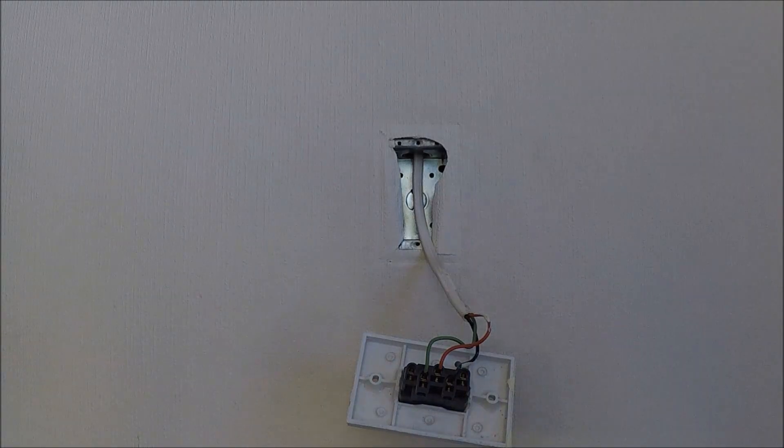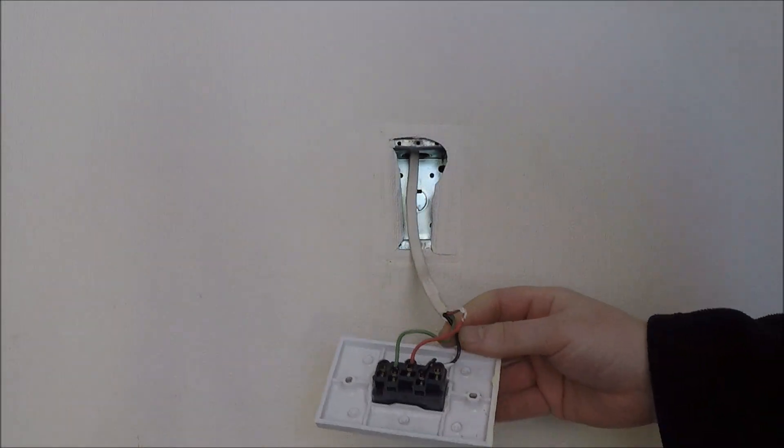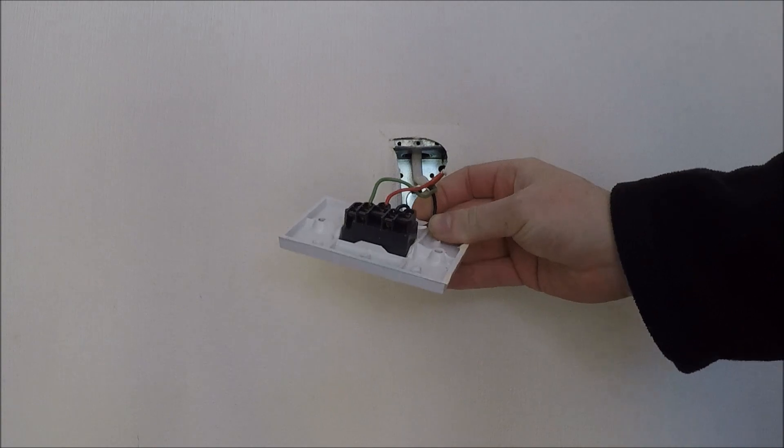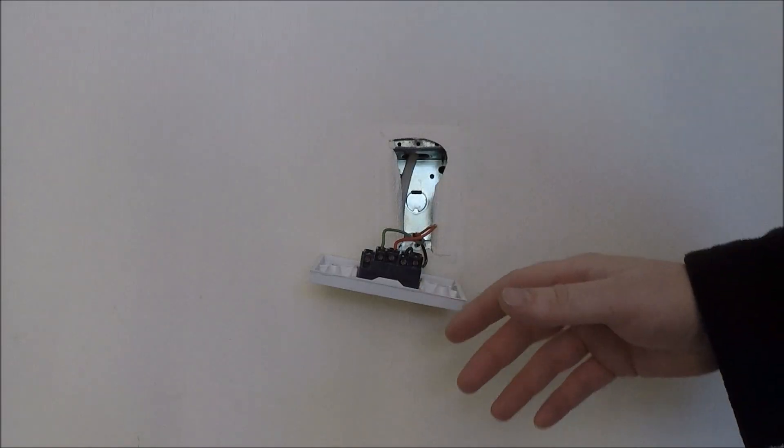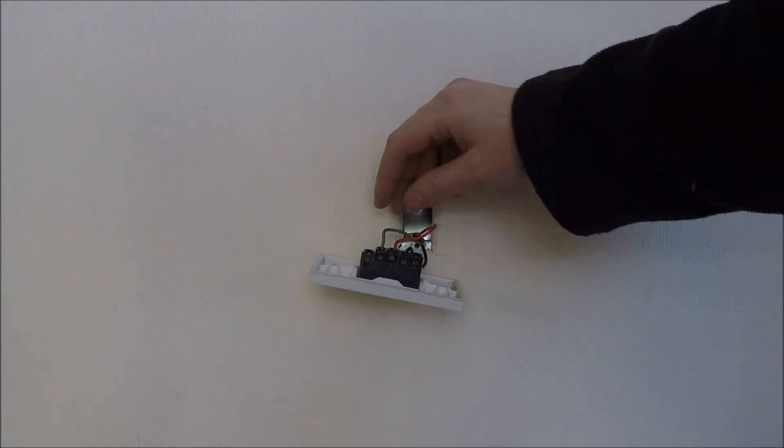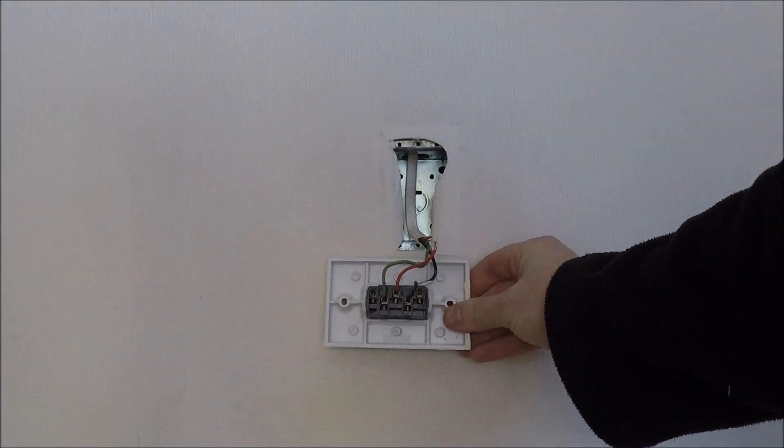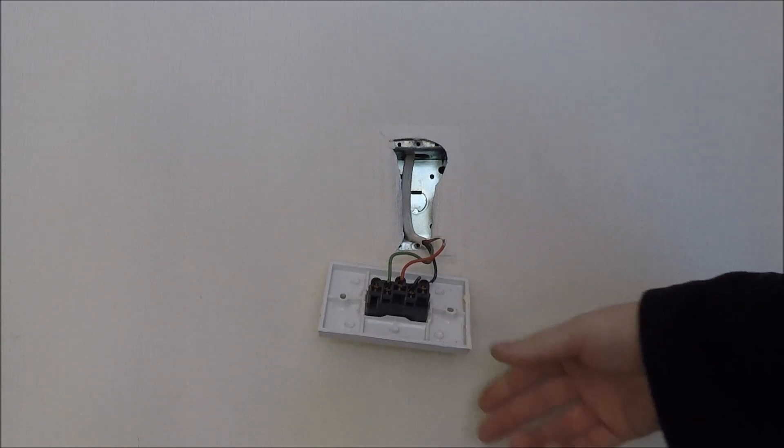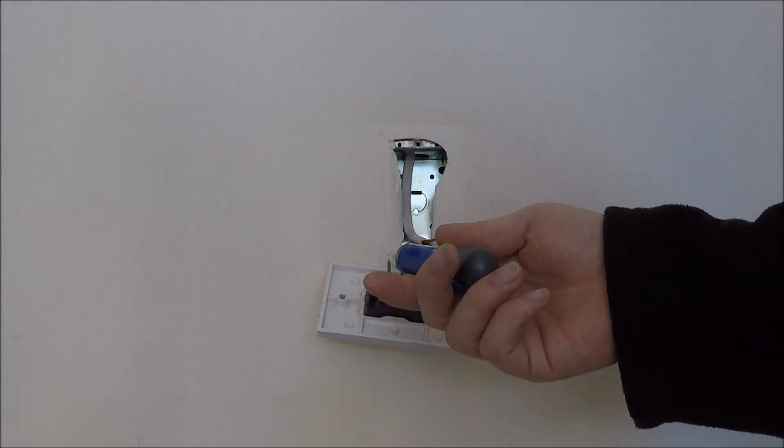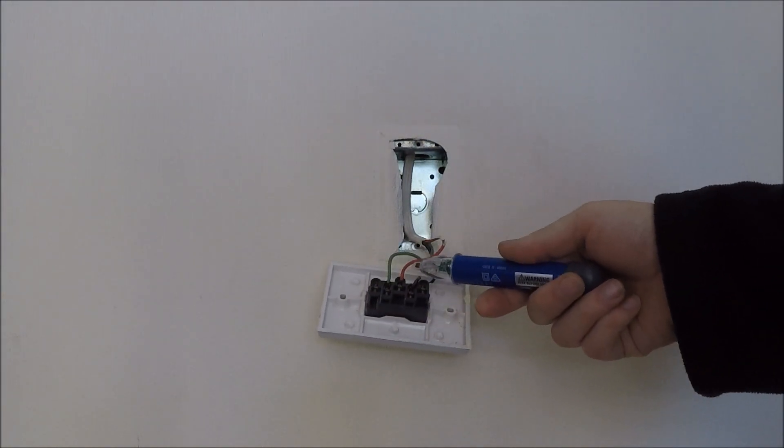Right, there's an old two-way switch. As you can see, they've used the green and black wires as active cables. So what we'll be doing is we'll put a bit of red sleeving over these, just to identify them for the future. Now turn my volt stick on. They're all dead.